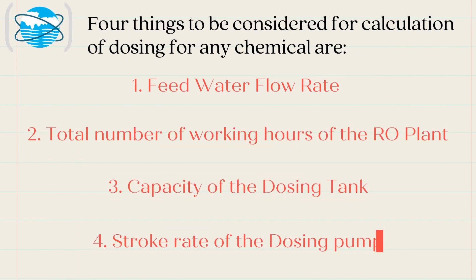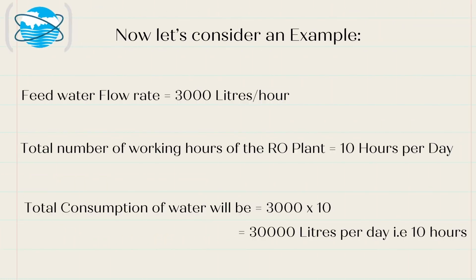Four things to be considered for calculation of dosing for any chemical are: 1. Feed water flow rate. 2. Total number of working hours of the RO plant. 3. Capacity of the dosing tank. 4. Stroke rate of the dosing pump. Now let's consider an example.